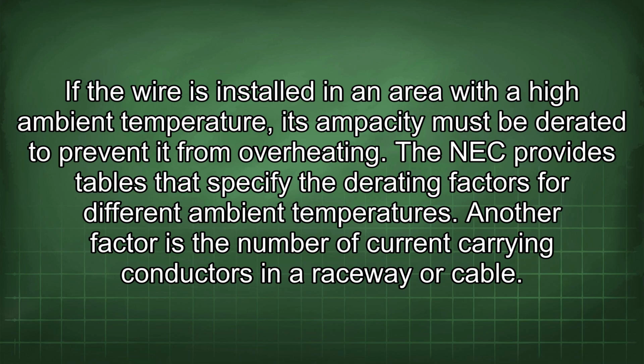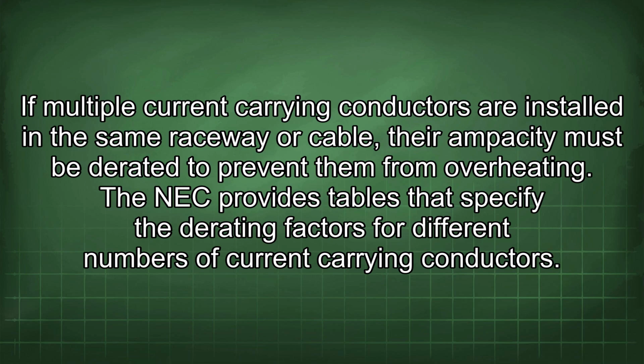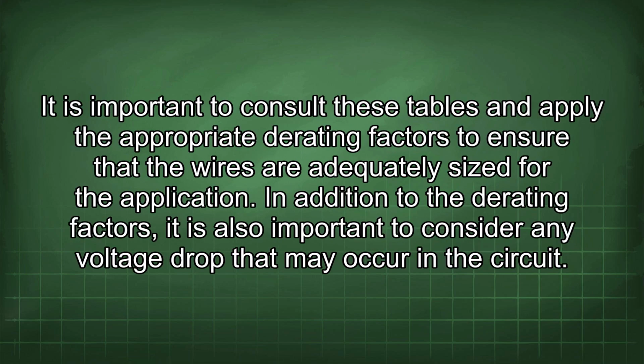Another factor is the number of current carrying conductors in a raceway or cable. If multiple current carrying conductors are installed in the same raceway or cable, their ampacity must be derated to prevent them from overheating. The NEC provides tables that specify the derating factors for different numbers of current carrying conductors.